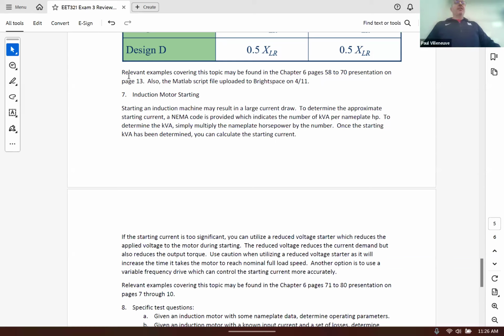And part of the reason is there's something that starts a motor called a motor contactor. Essentially, these are the three AC lines that feed the motor. Normally, we run two of those lines through a control power transformer, and that feeds a bunch of stuff that will help us start the motor. If the voltage drops to below 90%, you get a dropout. Your voltage is not sufficient to maintain the connection, the devices in there. And so it stops and doesn't do it.